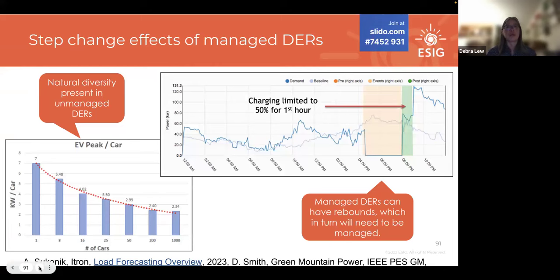Fundamentally, what we're talking about is how do we manage the DERs. Prior to any management, like that third category Jill showed of not managing DERs, we've got natural diversity across loads, which is a great thing. This is why we can undersize equipment compared to the total nameplate rating of the loads. One EV charging needs its full nameplate rating, but 1,000 EVs charging need much fewer kilowatts per car because of the diversity.